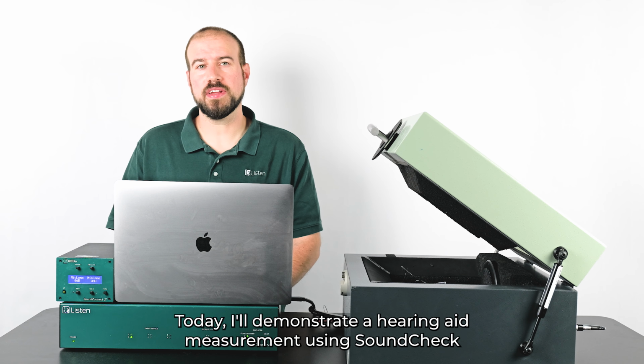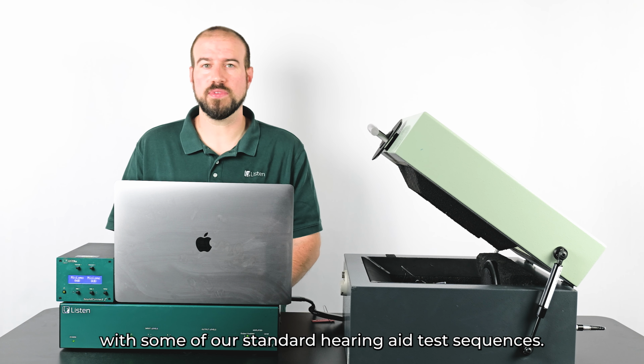Today, I'll demonstrate a hearing aid measurement using SoundCheck with some of our standard hearing aid test sequences. We'll use some of the tests outlined in the ANSI S3.22 hearing aid test standard: frequency response, input-output linearity, OSPL90, and release time. First, let's take a look at our hardware setup.